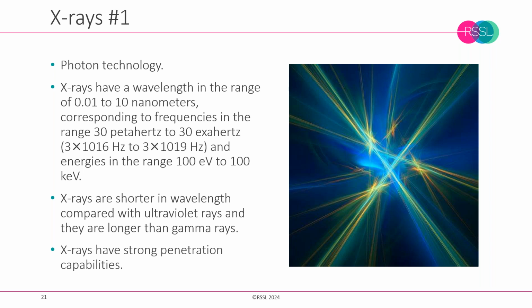Moving on to X-rays, anyone dealing with the change control process may well have noticed that in the last couple of years a number of manufacturers of these sorts of technologies have been requesting switching from gamma radiation to X-ray. So X-ray is no longer an alternative or less popular technology. It's increasing in scope, and the reason for this is that the cost of gamma radiation has increased because of the scarcity of getting hold of cobalt-60. So things like E-beam and X-ray are being looked at more often.